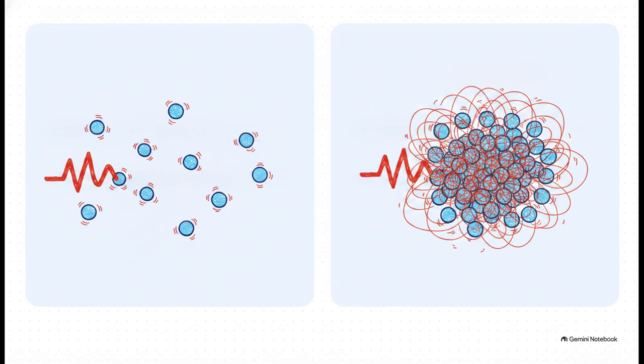The fundamental solution to this bottleneck comes down to basic physics: we simply need a better medium to capture and carry away heat. Think about air for a second. It's a gas, its molecules are widely spaced apart, and because they're so far apart, air is frankly terrible at absorbing heat efficiently. Now contrast that with liquid. Liquid molecules are densely packed together. This simple physical difference means liquid has a drastically higher heat transfer rate. When a hot surface touches a liquid, those tightly packed molecules can absorb and carry away thermal energy at a rate that air could never dream of matching.